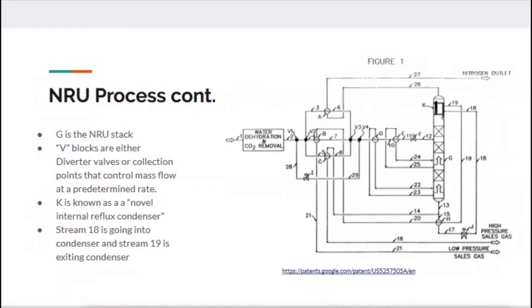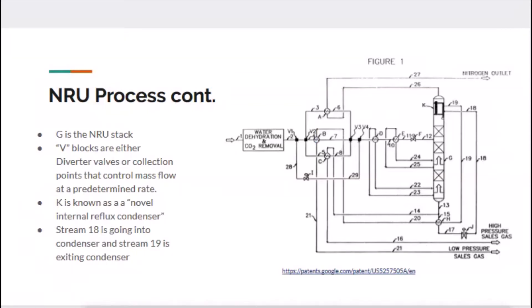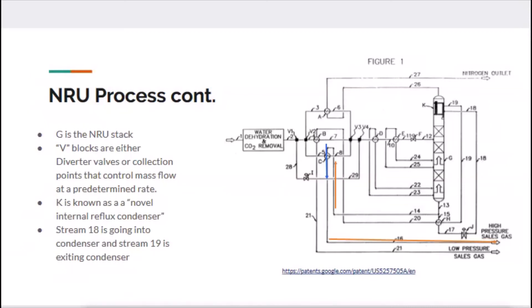Following stream 19, it goes through this heat exchanger, comes up here, and continues on. It'll be used to cool stream 8 right after V2, then continues down around the corner to become the low-pressure sales gas. Stream 18 goes into the condenser. All the heavy hydrocarbons fall to the bottom—you see stream 13 there. A little bit gets bled off, continues on to cool that stream in heat exchanger C, then becomes the high-pressure sales gas going out.